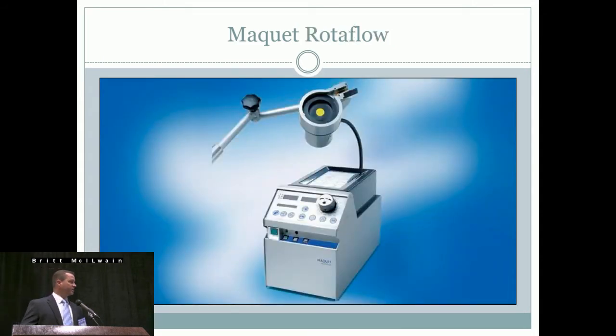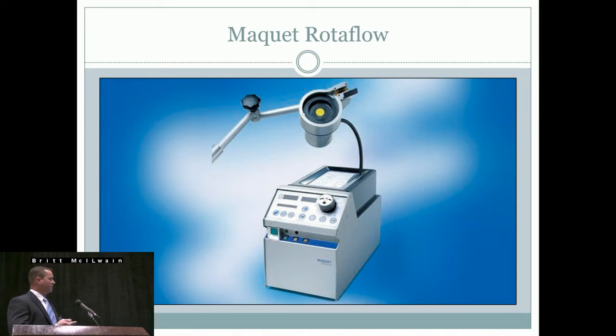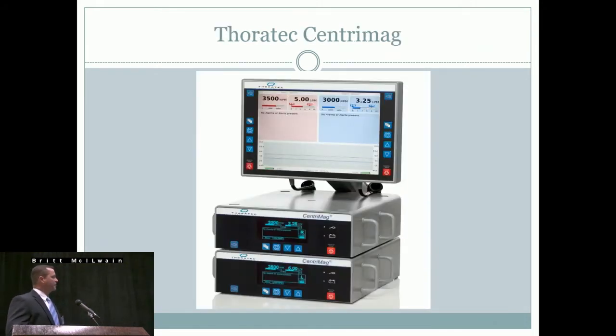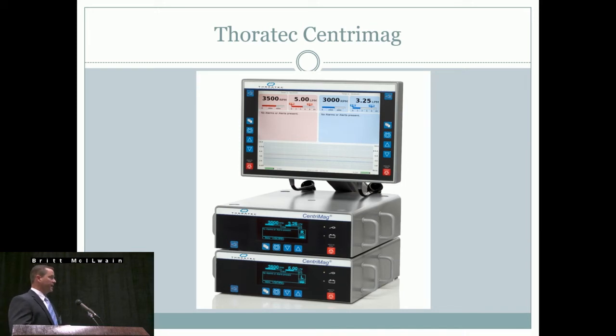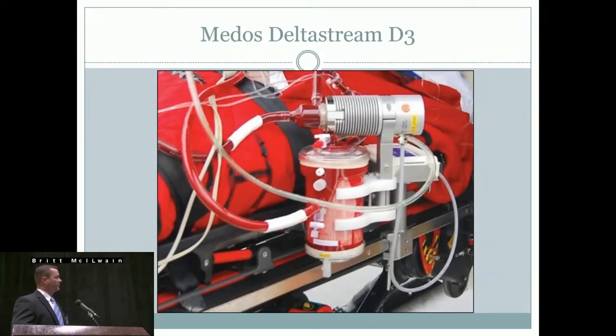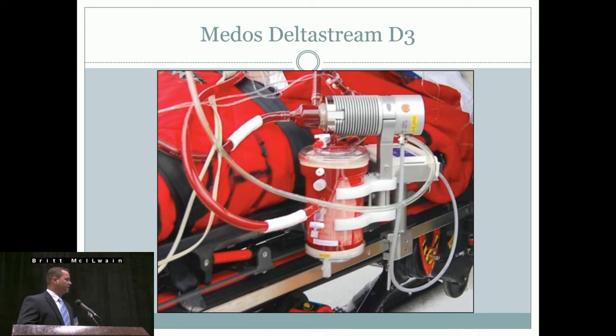Other equipment people use includes the Maquet Rotaflow, and it's important to note that the Maquet Rotaflow has a hand crank so you can provide support during an emergency or disposable failure. We also have the Centrimag in-house, though we don't use it for ECMO transport. It has no hand crank, so you'd just need to take a backup controller. We like the CardioHelp because it has integrated interventions and safeties. The Medos Delta Stream is also a good option in Europe, though not yet available in the States.